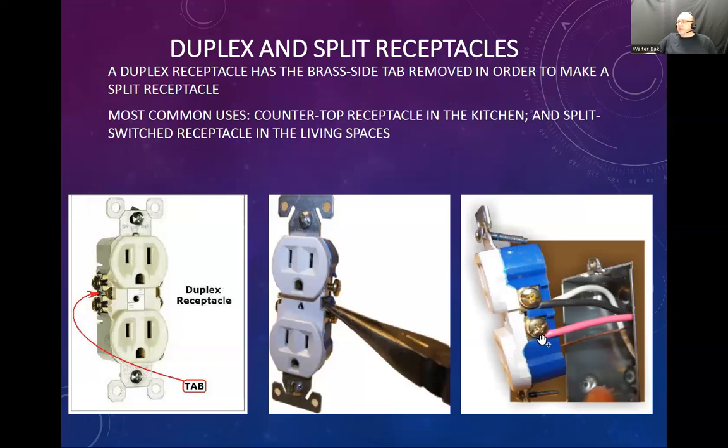And the other hot, which would be red in this case, would be connected to another circuit breaker. So you could have 15 amps in here and 15 amps available for here. Again, you should watch the gauging, because sometimes you need to up the gauge of the wire in order to be able to do that kind of stuff. Or you can use 2 wires and split the other one as well. So you can do that.